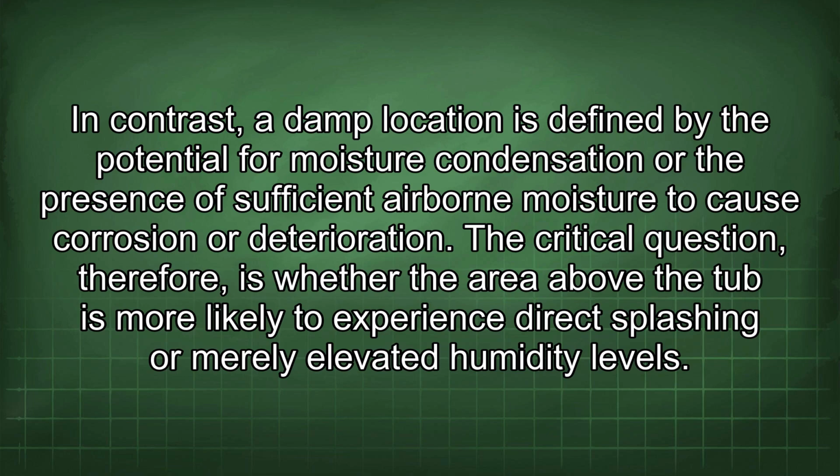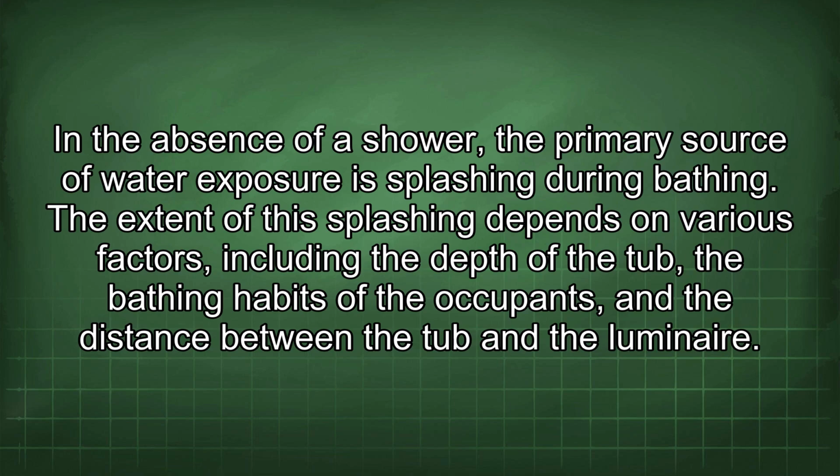The critical question, therefore, is whether the area above the tub is more likely to experience direct splashing or merely elevated humidity levels. In the absence of a shower, the primary source of water exposure is splashing during bathing. The extent of this splashing depends on various factors, including the depth of the tub, the bathing habits of the occupants, and the distance between the tub and the luminaire.